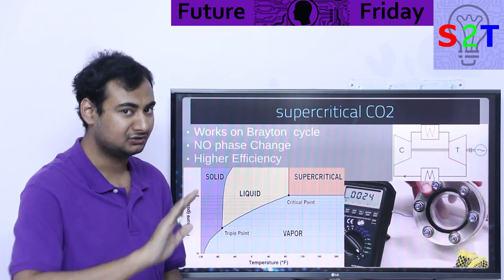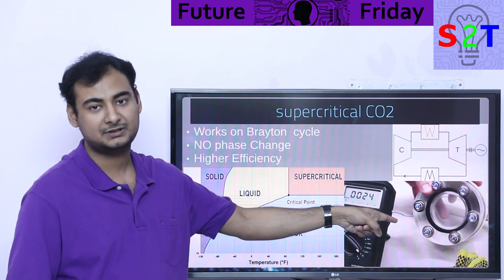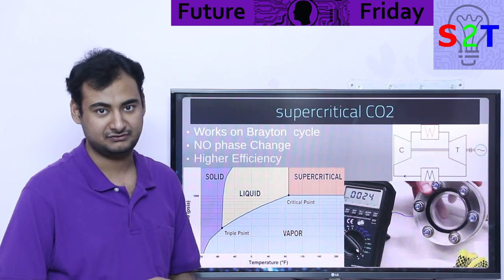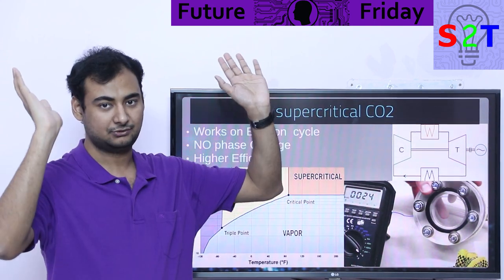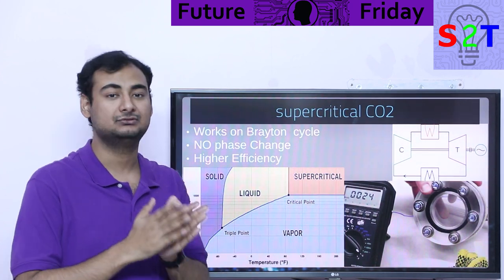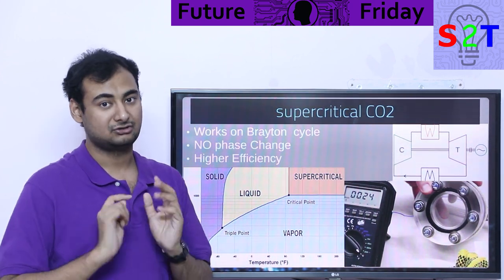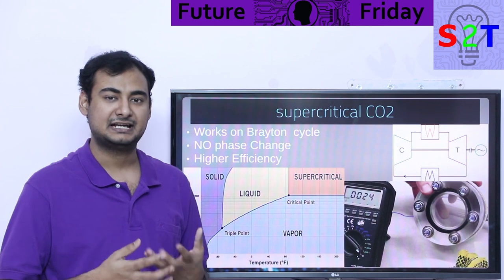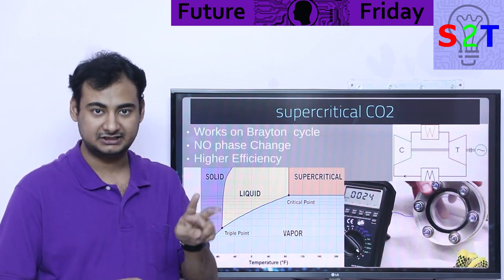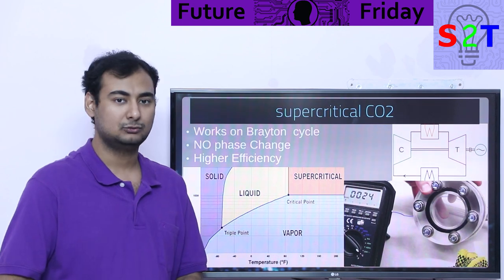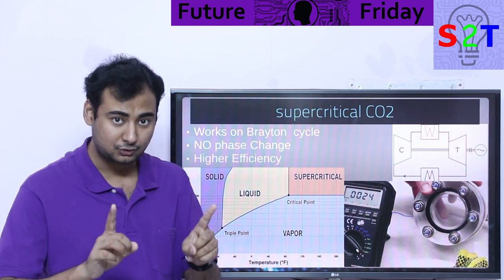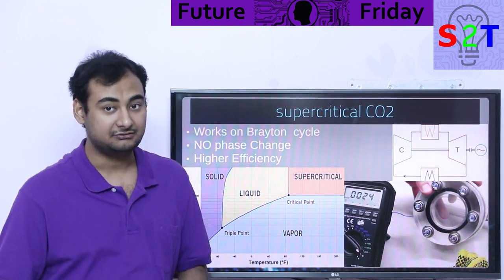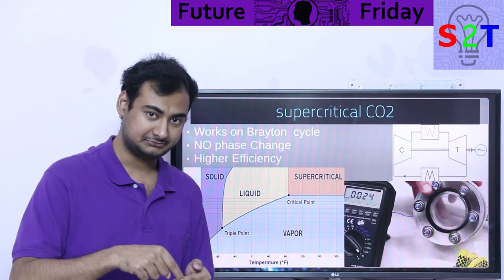No phase change is very critical — you do not want to change phase. To maintain supercritical carbon dioxide, you have to close the loop. Nothing leaks into the atmosphere; there are no giant cooling towers. You have to design heat exchangers so you only exhaust the heat, not the working fluid. Everything has behavior directly proportional to two core criteria: pressure and temperature. In school, we learn carbon dioxide doesn't go to a liquid phase — that's true at sea level at 15 psi. But if you compress it enough, you can make it into a liquid.